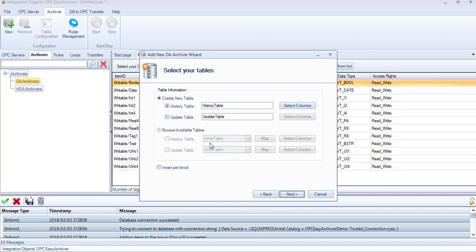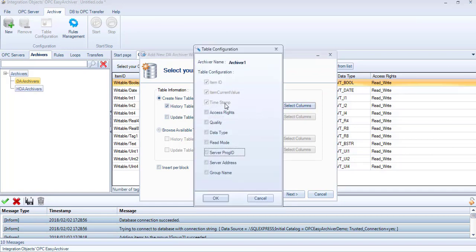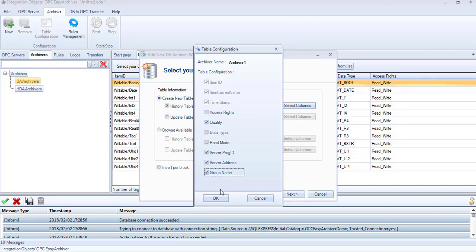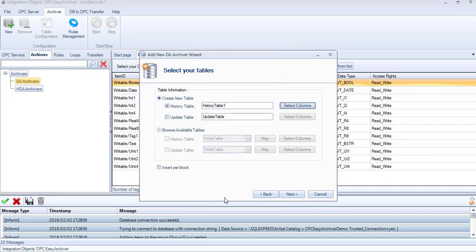In this step, we need to configure the tables where the OPC data will be stored. You can either create new tables or select existing ones. The history table is used to store all of the received data values, and the update table is used to store only the last received values of the OPC tags. For the new table option, select the table name and click the Select Column button to add columns to your table. Click Next.